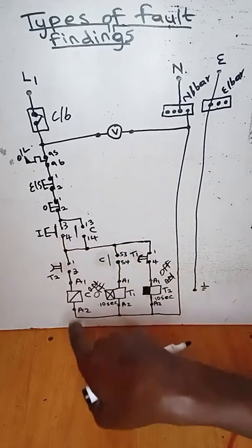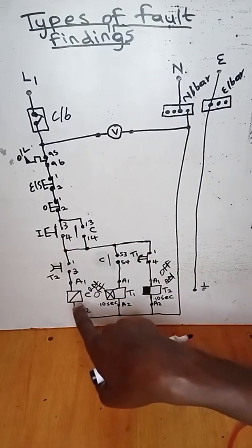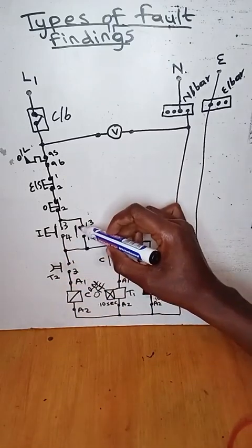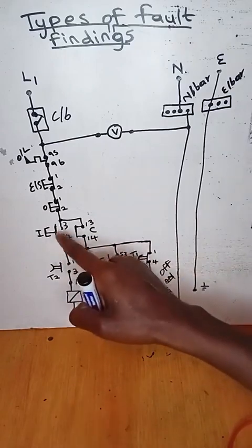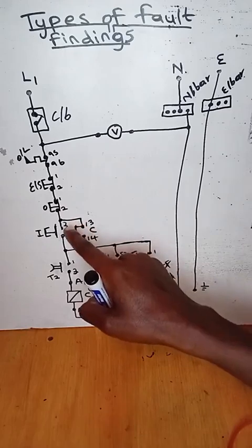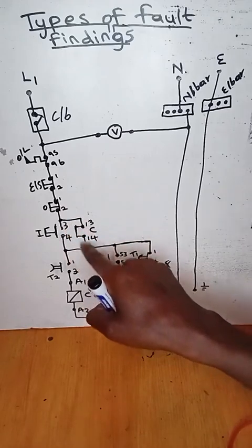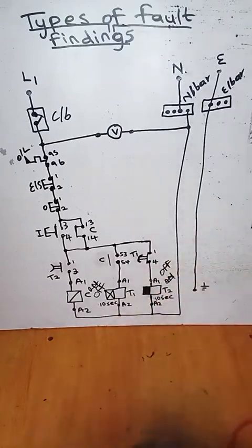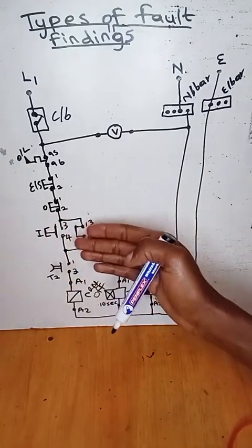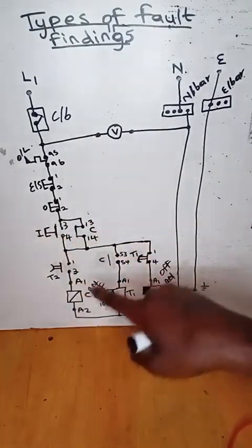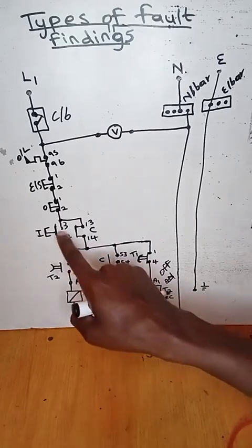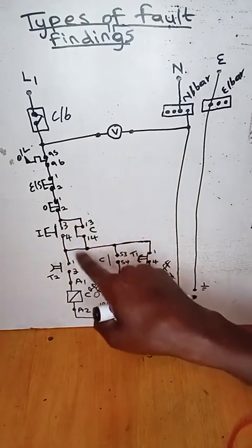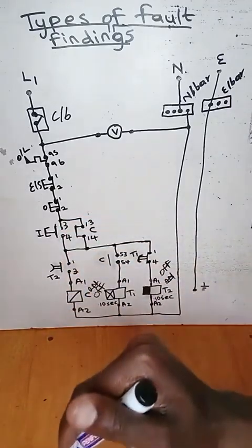After pressing that button, the coil of a contactor must be energized and the coil of delay of timer must be energized, in which it has to affect this contact to be closed, and after letting the start button go, the current must be held through the retainer of a contactor so that it can supply from where it supplies, right? So if you get that fault whereby you push the start button, a coil becomes energized, and after letting it go, it becomes off immediately, it simply means there's no retainer that holds the current after pressing the start button, right?